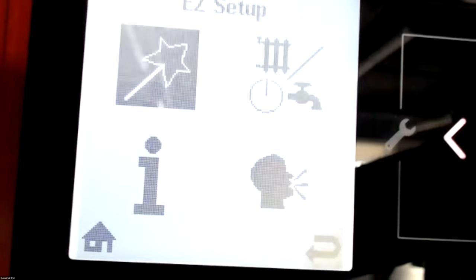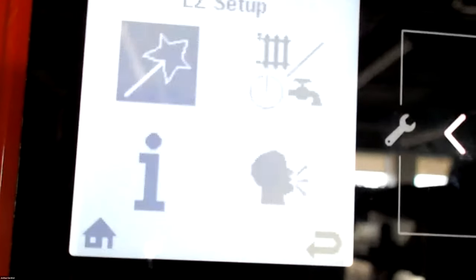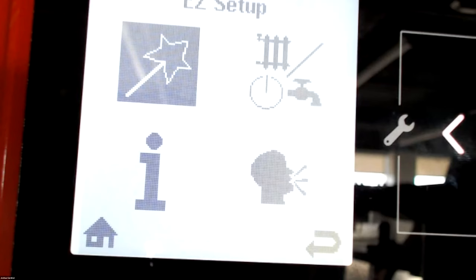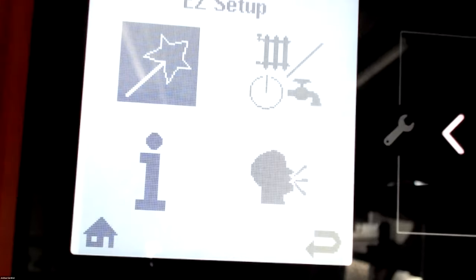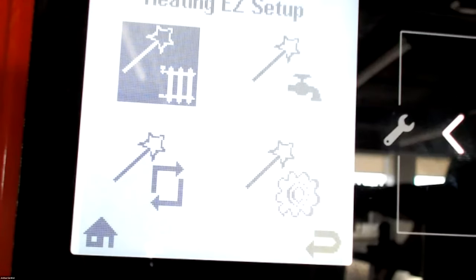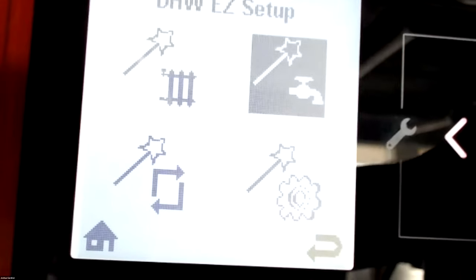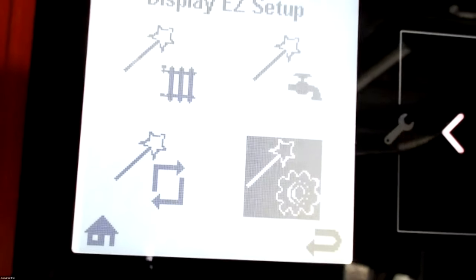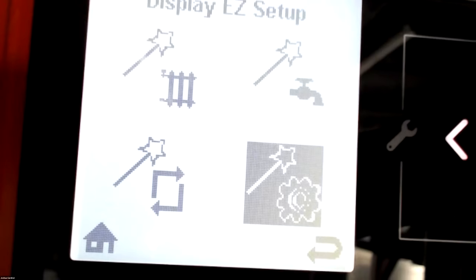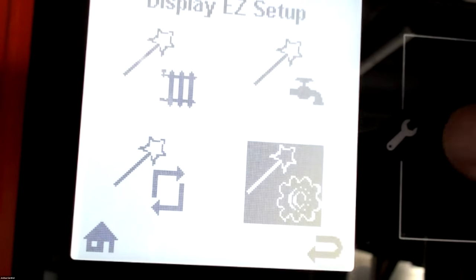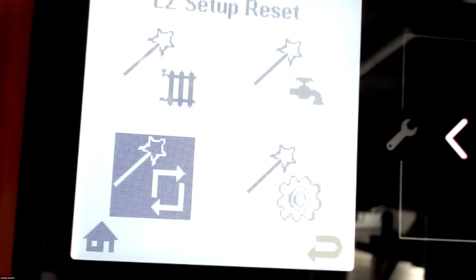The boiler info. Now the easy setup. So this easy setup is good. It gives you a quick setup if you're doing just thermostat and set point and not doing the curve. But for most cases, I'm still going to recommend that you guys adjust the curve in the back end of the control, the installer settings, we'll call it. So the easy setup, you'll click onto that, and you'll have the heating easy setup, DHW easy setup, your settings, so you can just look at what is what, not control or change anything, and then your reset for the easy setup.